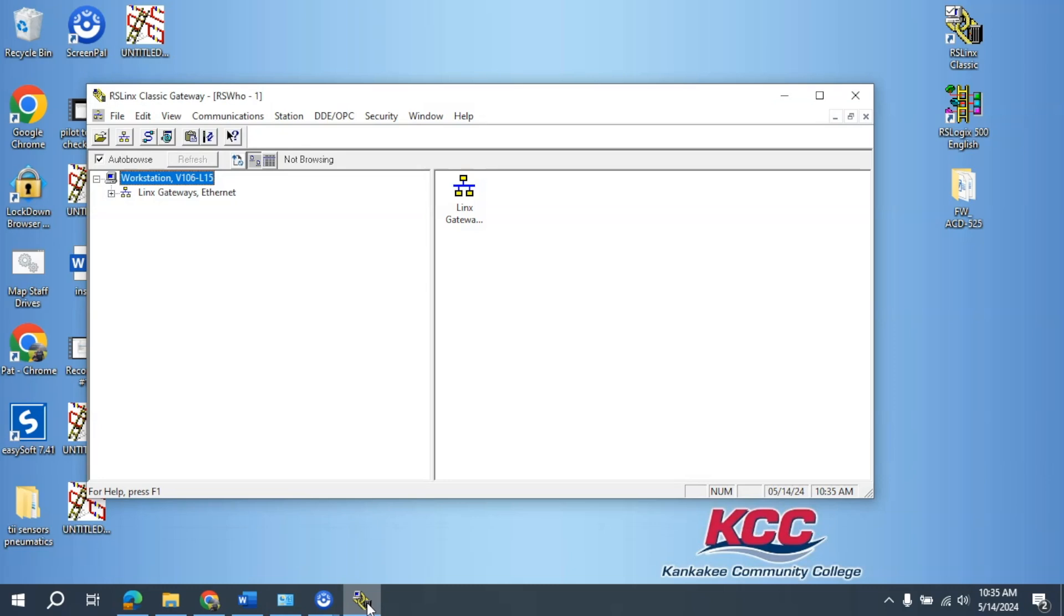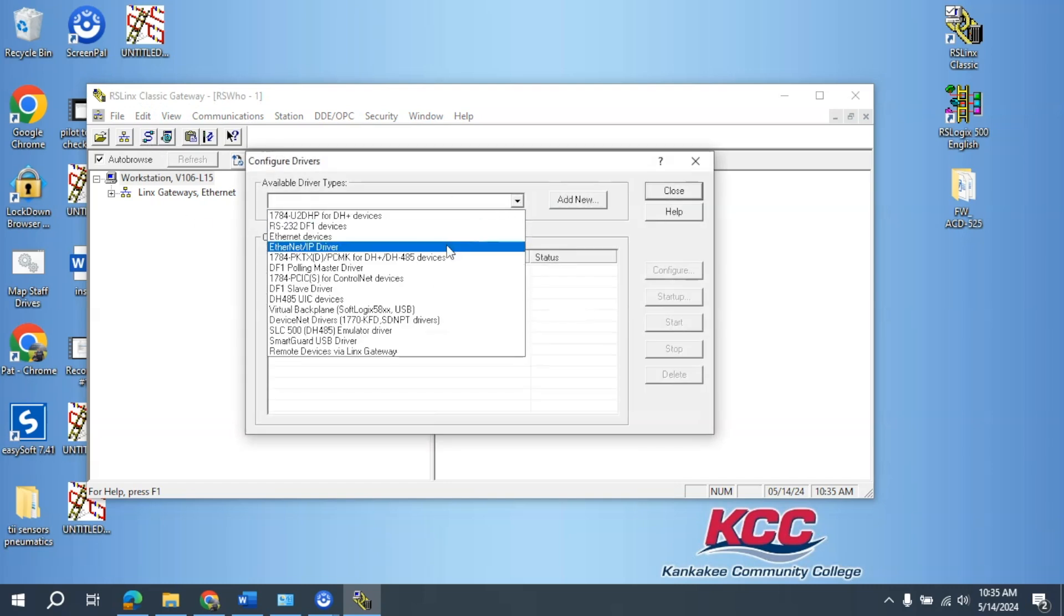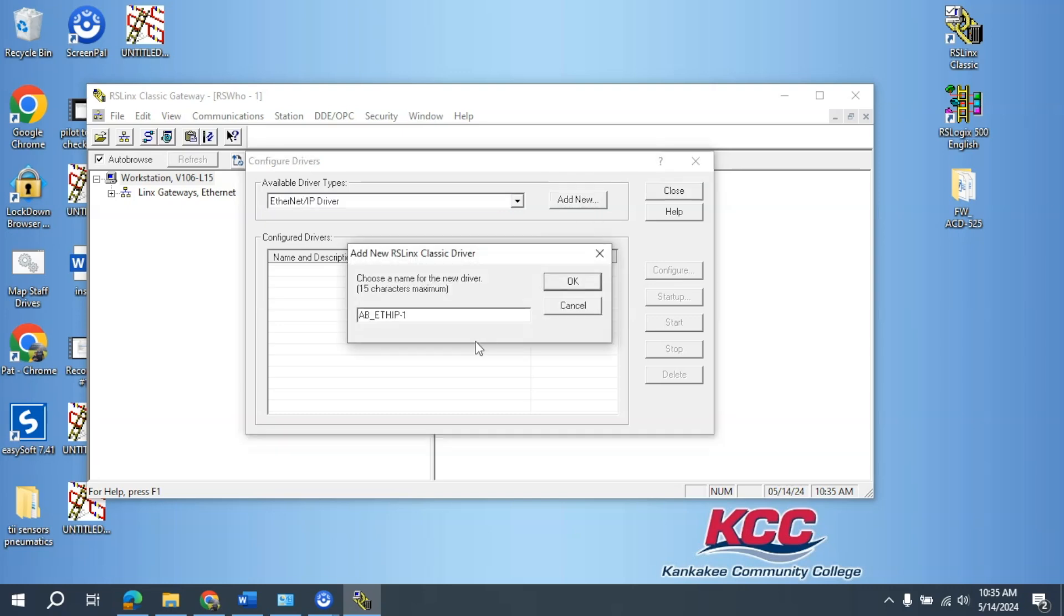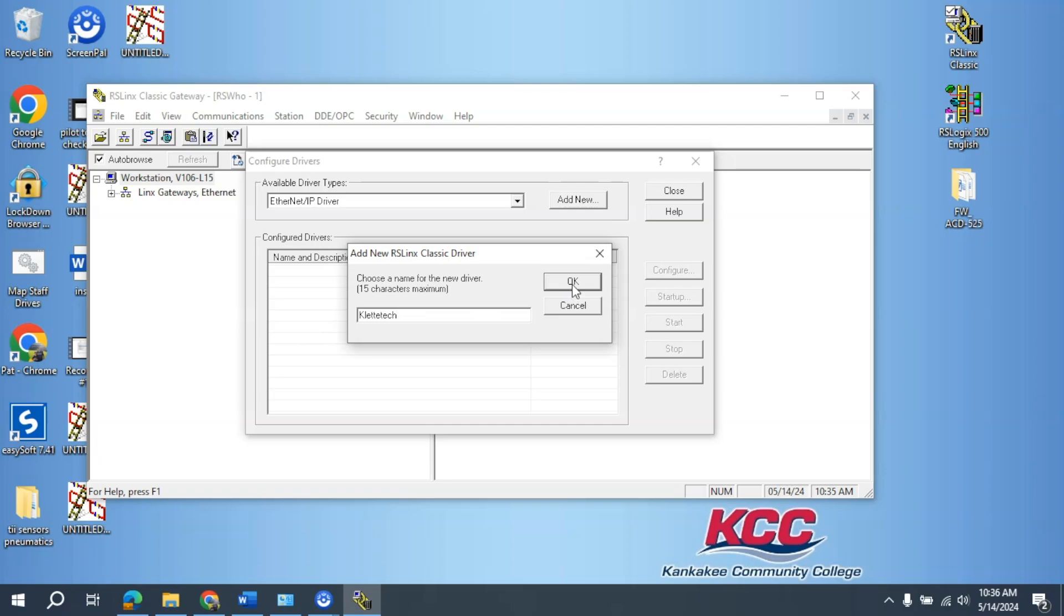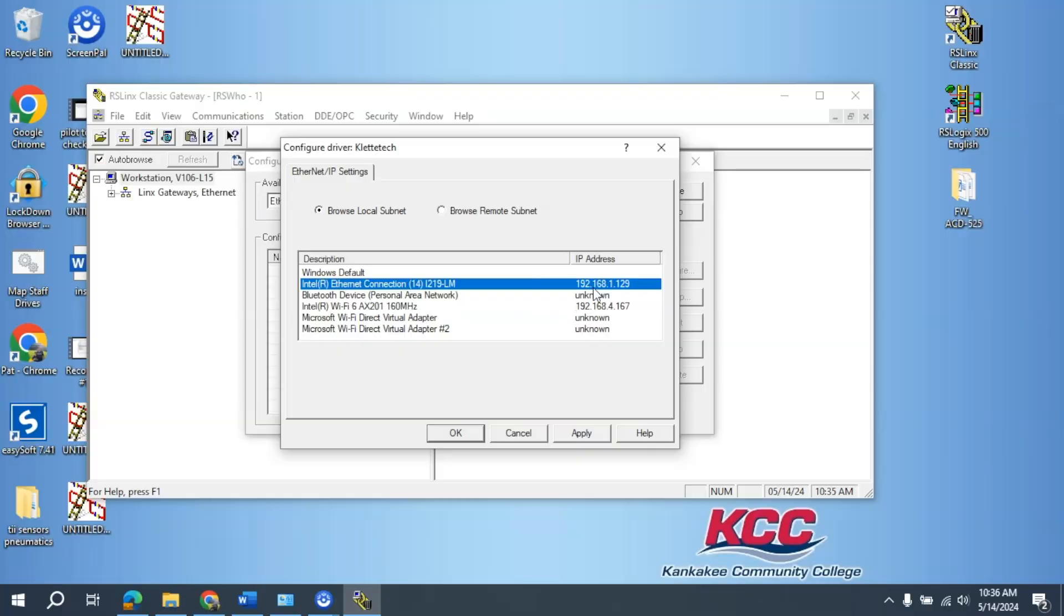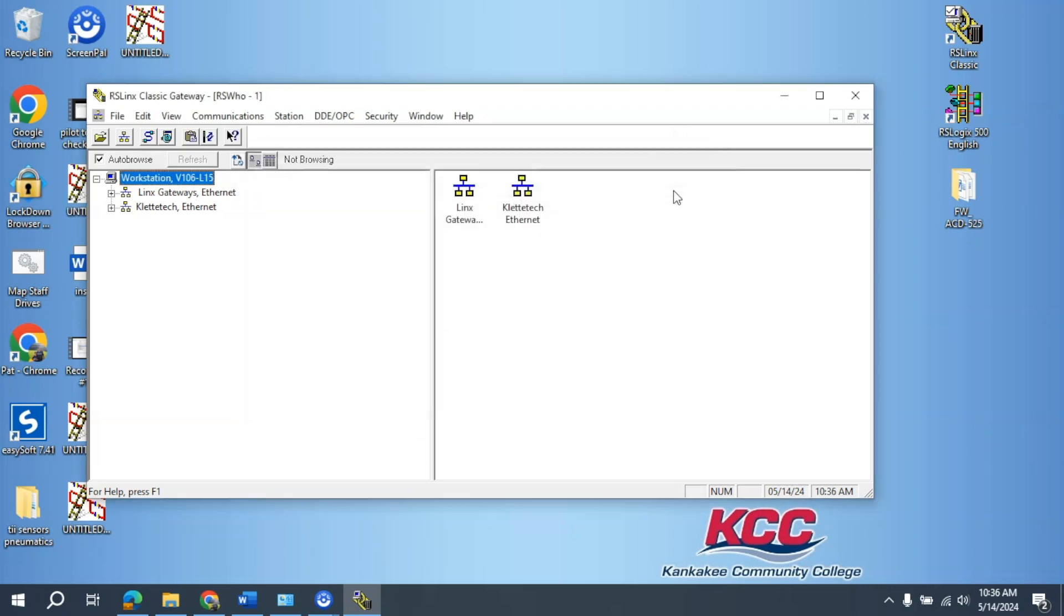I'm going to go into RSLinx Classic and open this up. Go to Ethernet Drivers, Ethernet IP Drivers, select Add New, enter in a recognizable name for the driver, select OK. Select the IP address that I've set for this computer, select OK, close out.